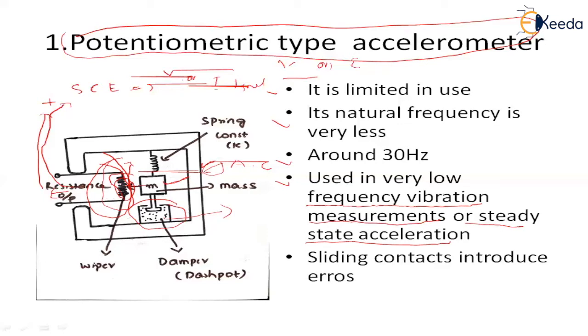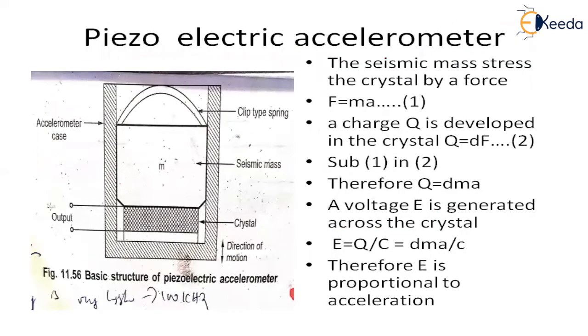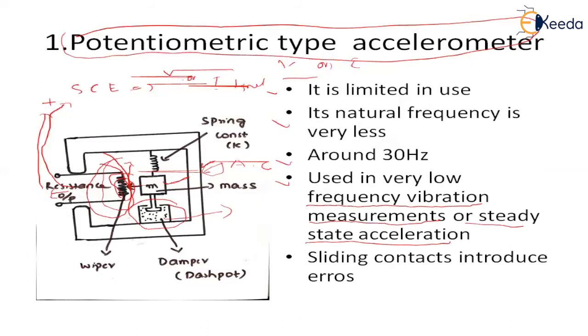So this method is used only for low-frequency vibration measurement or steady-state acceleration. The disadvantage is the sliding contact which introduces errors. That is the reason we move to the next method — the disadvantages of the existing method will be compensated by the next type, which is the LVDT type accelerometer.